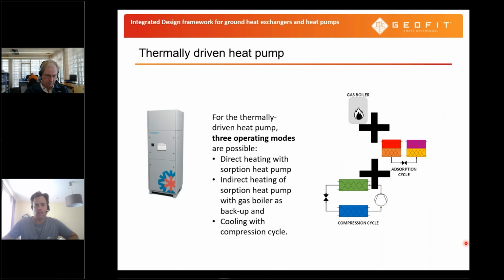The thermally driven heat pump consists, as I mentioned before, of a gas-driven sorption heat pump. This system is coupled to a compression cycle in order to provide the heating and the cooling at high efficiency, and also making use of shallow ground source heat exchangers.